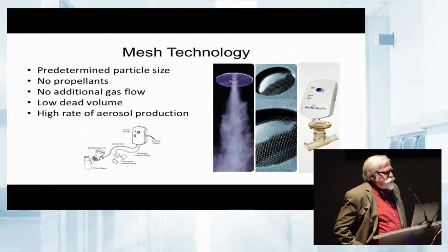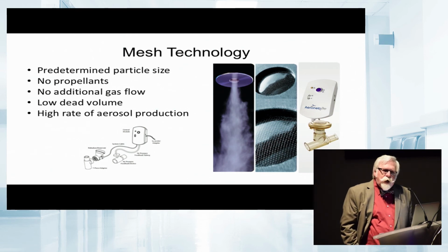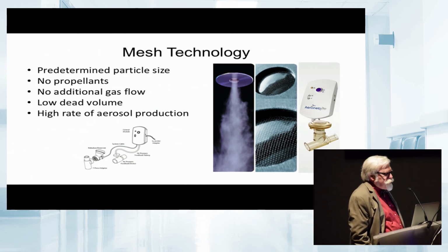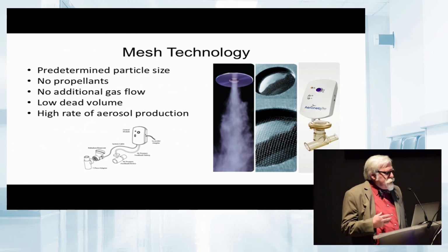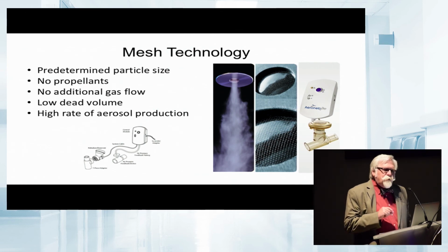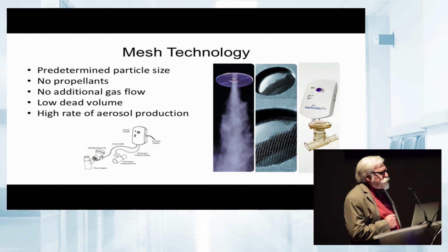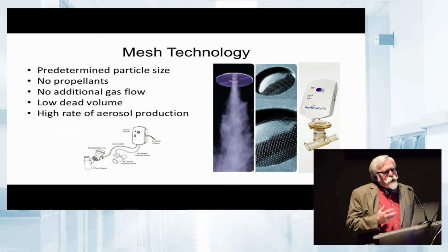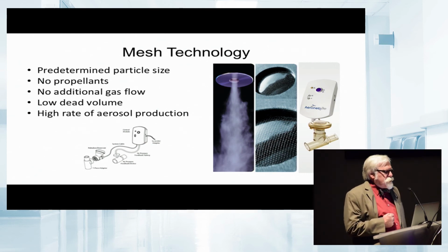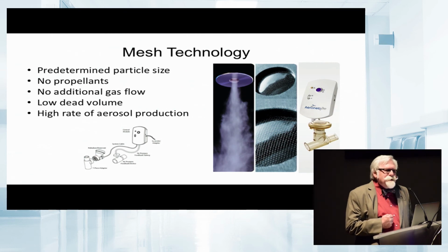With mesh technology, there is a predetermined particle size determined by the size of the holes in the mesh. There are no propellants. There is no additional gas flow that is added into the ventilator circuit. There's very little dead volume, meaning that virtually all of the drug that we place into the nebulizer is delivered to the patient, and there is a very high rate of aerosol production. So we get around many of the issues with the jet nebulizer by using a mesh nebulizer, and this is increasingly used throughout the United States and I suspect around the world.